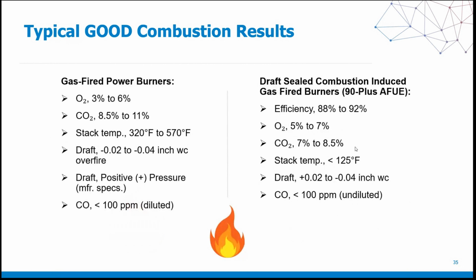Typical good combustion results for a gas-fired system, that's the 3 to 6%. Again, CO under 100 ppm. But we've talked a lot about high efficiency or condensing systems. Your efficiency ratings here are 88 to 92%. It's actually higher nowadays, up to 98% now. But we have oxygen anywhere from 5 to 7, CO2 from 7 to 8.5, and CO again at under 100 ppm.